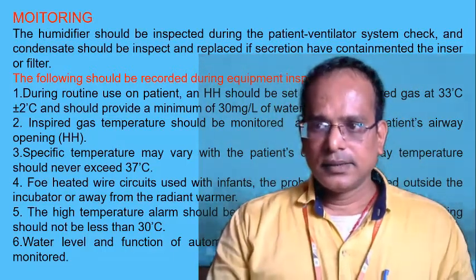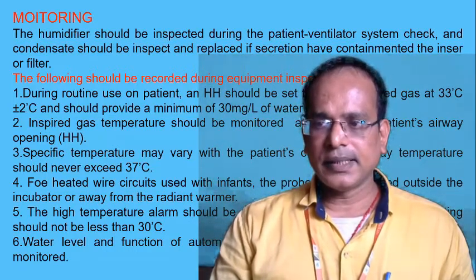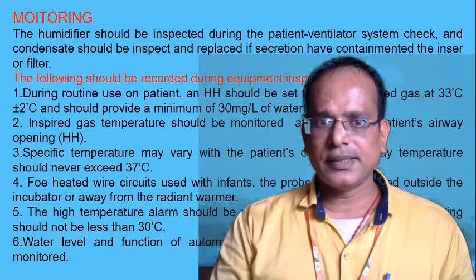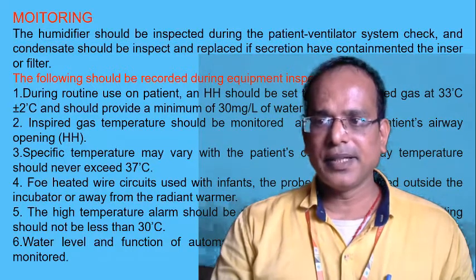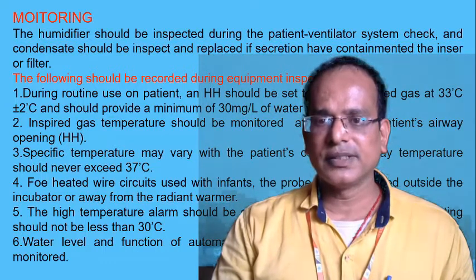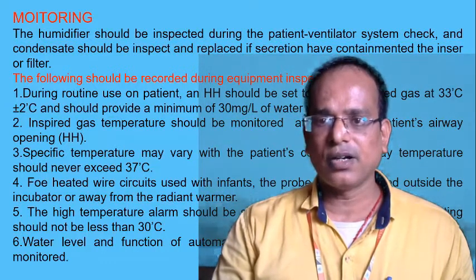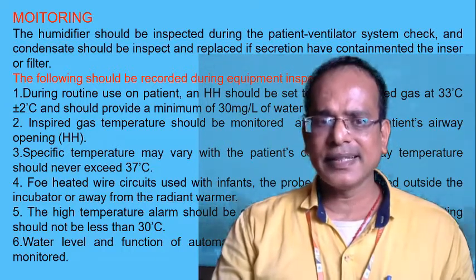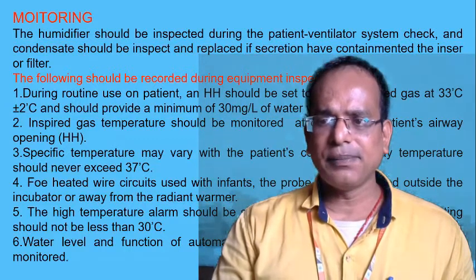31 degrees Celsius, and should provide a minimum of 30 mg per liter of water vapor. Second, inspired gas temperature should be monitored at or near the patient airway opening during the HH, that is humidifier. Third, specific temperature may vary with the patient condition. Airway temperature should never exceed 37 degrees Celsius.